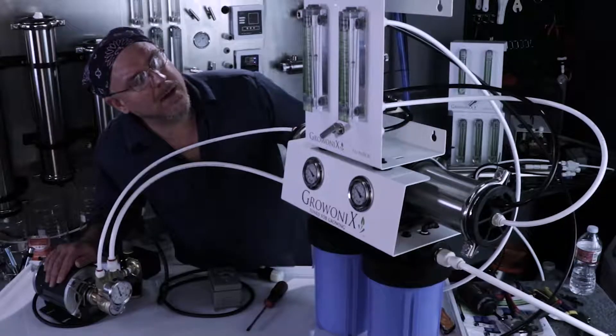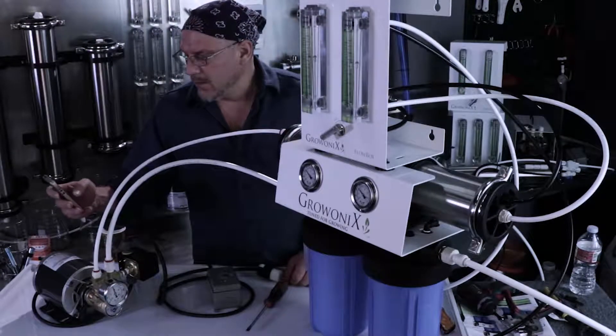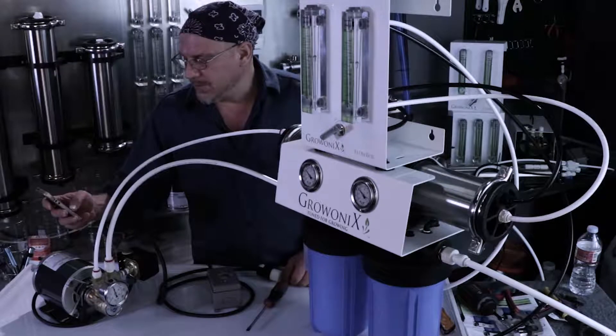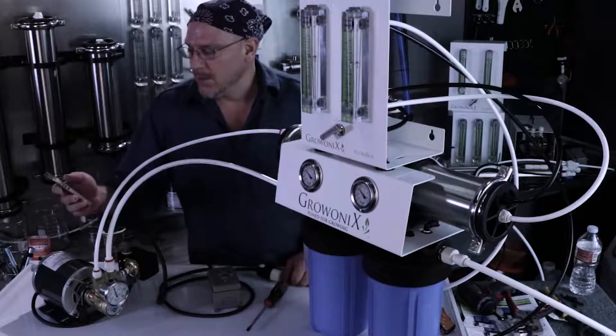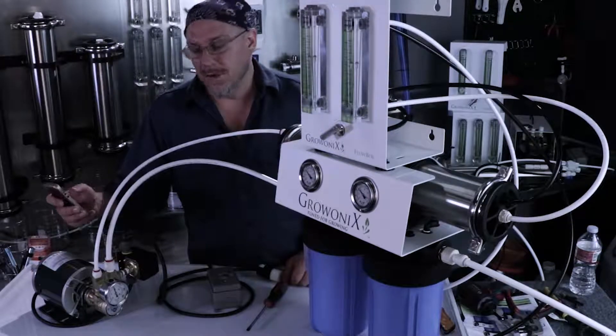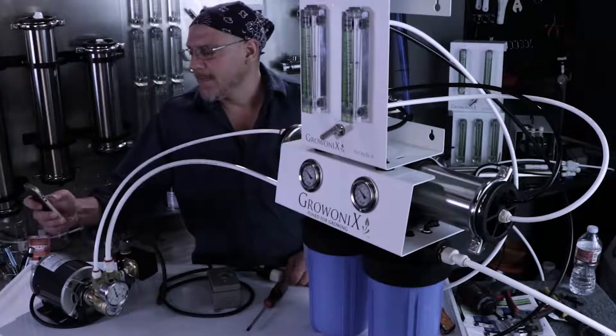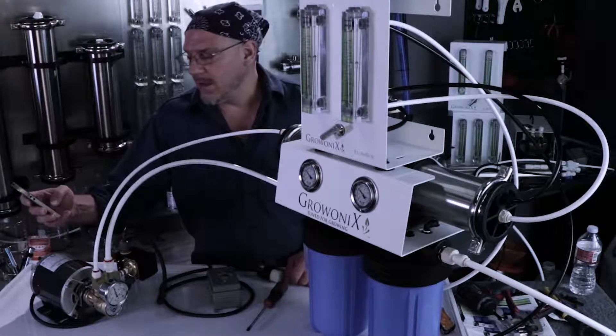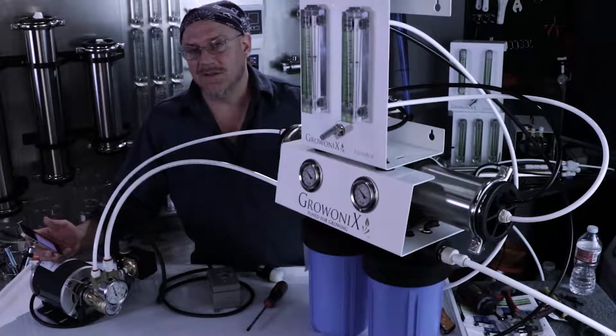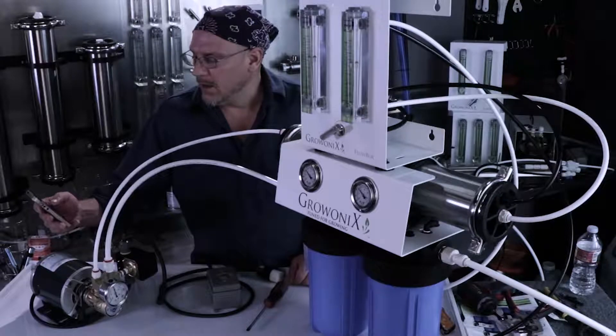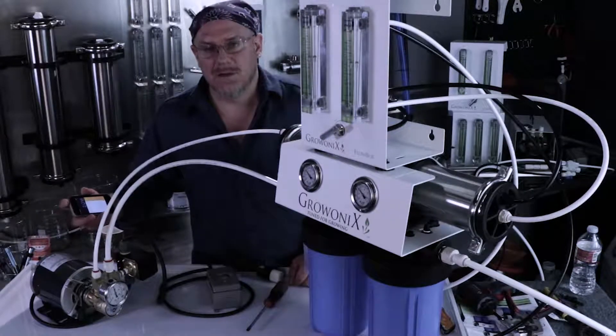We're putting out about 1.2 gallons a minute, and 1.2 times 1440 is about 1728 gallons per day. If I was running at 150 psi, which I'll be able to do when this water cools down in a few weeks, we'll be just over 1.4 gallons a minute on a brand new GXM 1000 HF high flow membrane, and that'll bring us to just over 2,000 gallons per day.